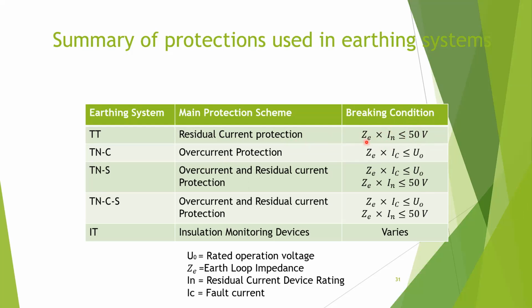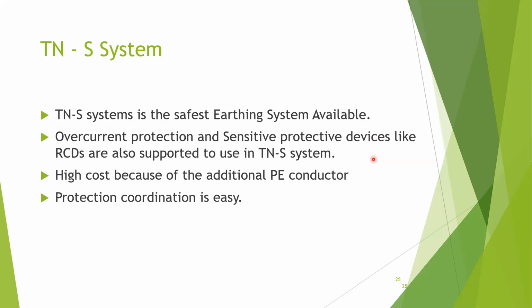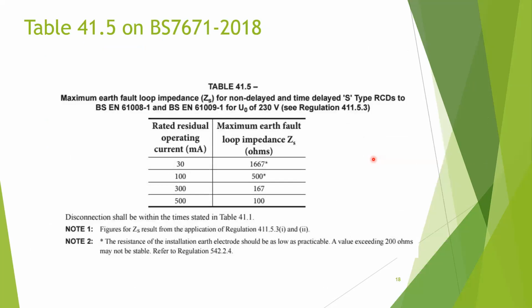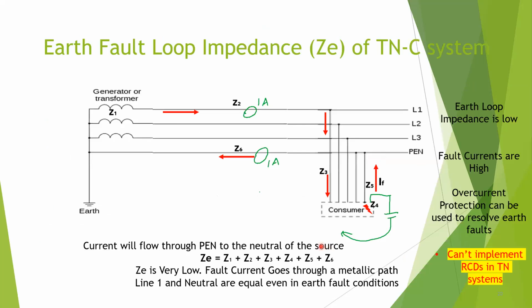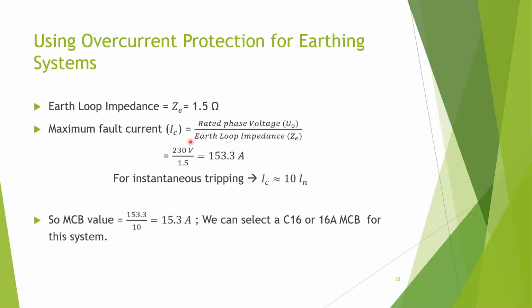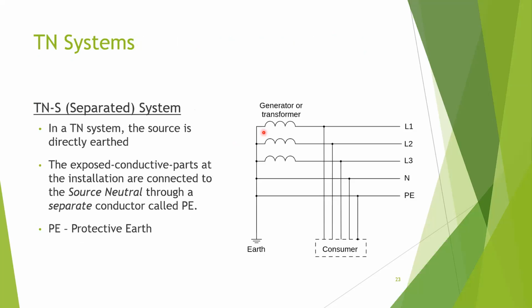So if IΔn exceeds the RCD value, your system will trip. And in a TNC system, you only have the overcurrent protection. In overcurrent protection, you are not considering the safe touch potential. You are considering the short circuit current, because as I told you, in a TNC system we cannot use residual current protection. What we are going to do is use overcurrent protection for the earthing system. So this is the equation we can use for tripping the circuit, that is what is mentioned there.